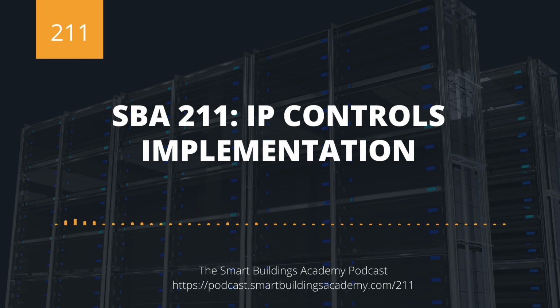So what we do is we bring those into a supervisory device via BACnet IP or whatever we decide to use. And we map all of those graphics into the actual supervisory device. Because at the end of the day, if we lose connectivity to the IP controller in an air handling unit, if this is an office building and not a hospital, then we're okay. We can go and run that thing in manual.